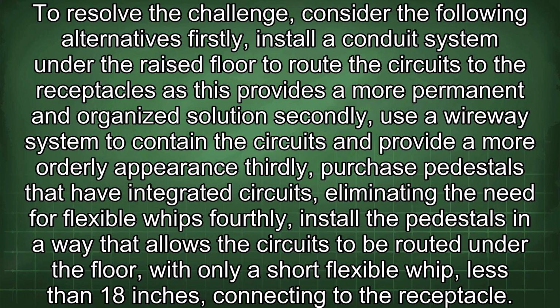Secondly, use a wireway system to contain the circuits and provide a more orderly appearance. Thirdly, purchase pedestals that have integrated circuits, eliminating the need for flexible whips. Fourthly, install the pedestals in a way that allows the circuits to be routed under the floor with only a short flexible whip, less than 18 inches, connecting to the receptacle.